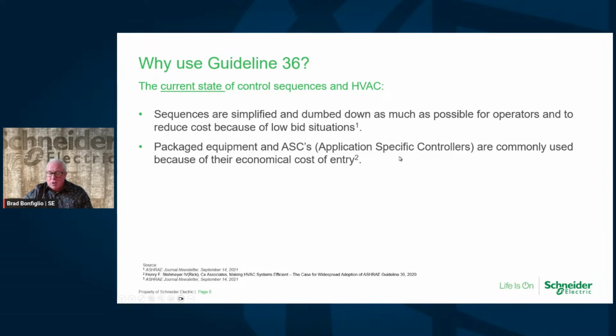The other current state of why it's not being used is a lot of packaged equipment. The actual Guideline 36 was related to chilled water, hot water applications. It is not related to DX units, rooftop units, that type of stuff at this stage. One of the challenges is when you're writing these sequences for high performance and you try to relate those to rooftop units and meeting some of the energy codes, there's a real challenge there because the application specific controllers that might come with the units can't do those sequences or are not programmed to do those sequences. So this is very common in the market. This is a real challenge for meeting this guideline.